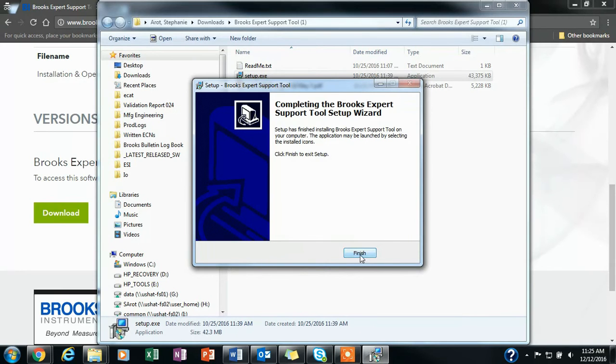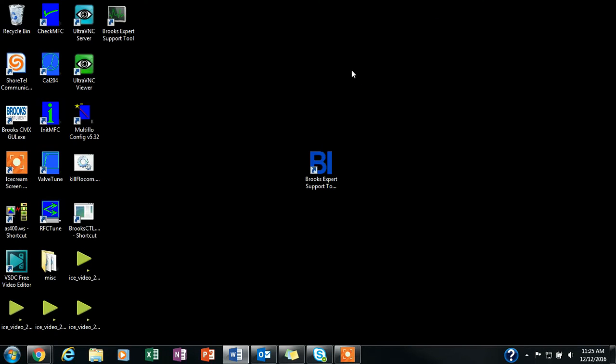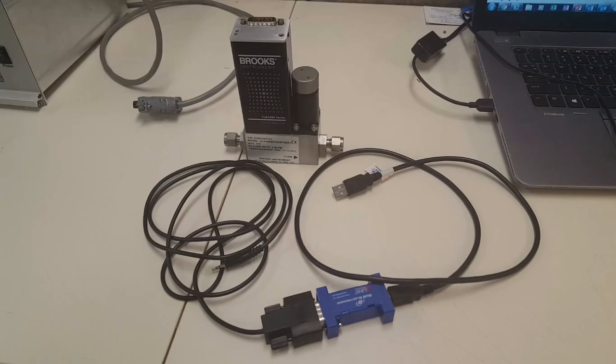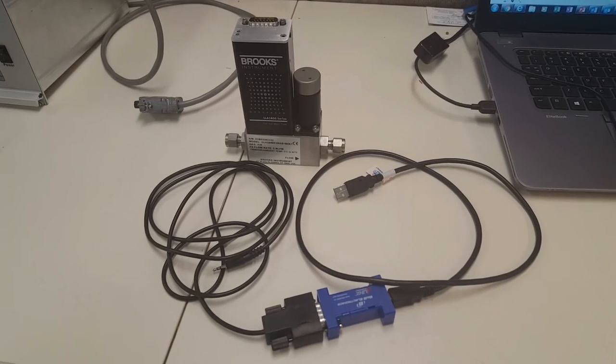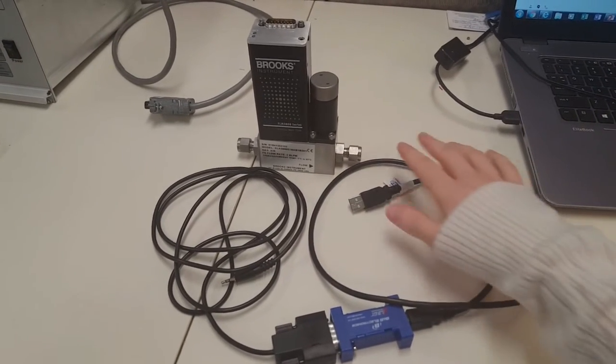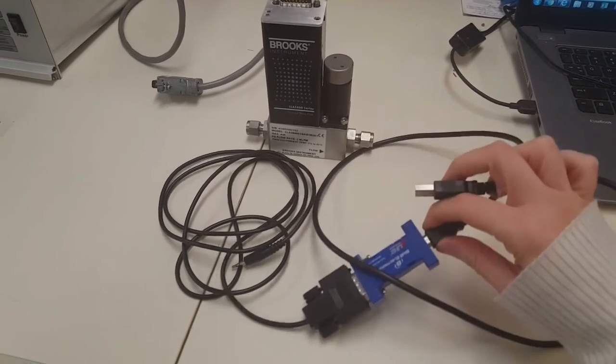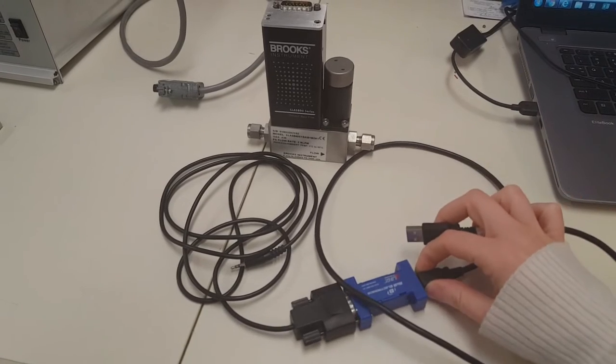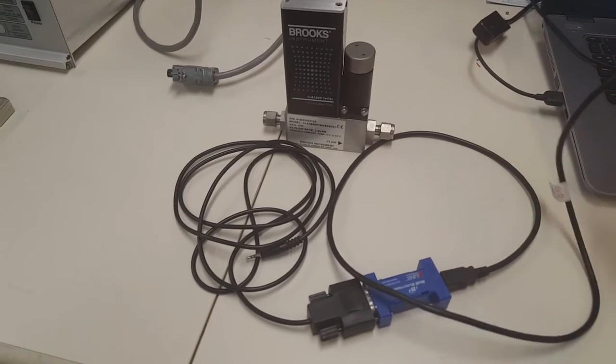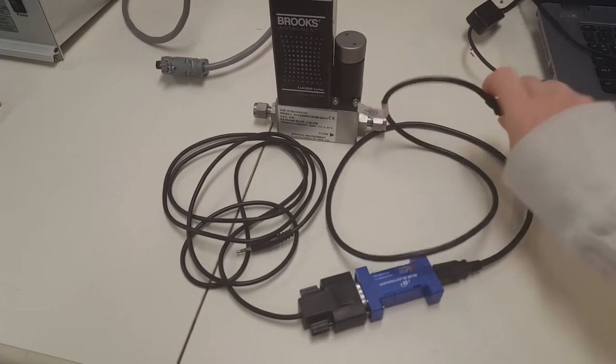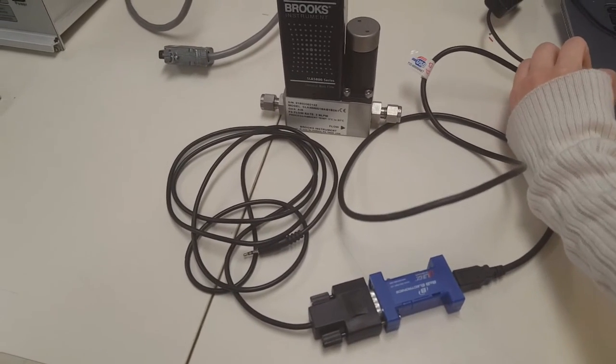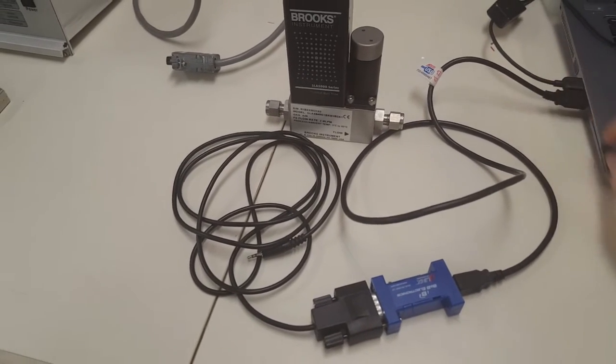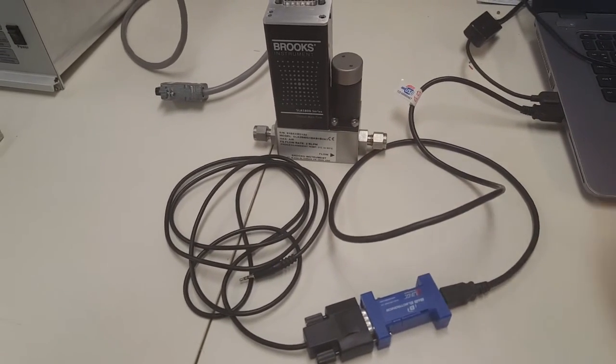Once the software is installed, you will need to connect your device to the PC. To physically connect the PC to the device's serial port, connect the RS-232 side of the RS-232 to RS-485 converter, or the USB side of the USB to RS-485 converter to a serial port or USB port on your computer.